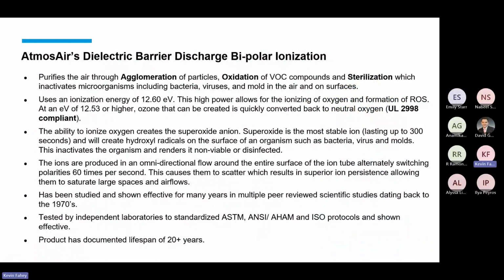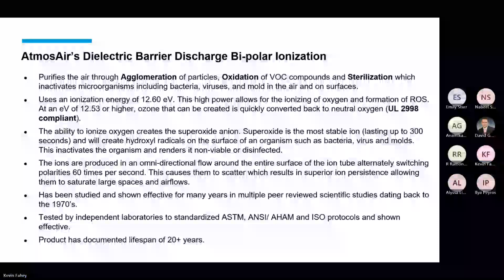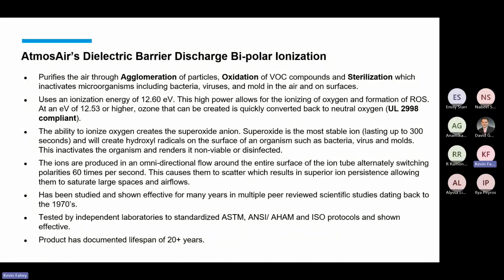Here it is. So three things. Agglomeration is particles getting larger. They either fall out of the breathing space, and I'm talking about nanoparticles, particles that are less than 2.5 microns in size. These are the particles that will get into your lungs and get into your bloodstream and really are irritants for people who have allergies and asthma, things of that nature. So it agglomerates these particles, they fall out of the breathing zone, or they're more easily picked up by a filter. ASHRAE did a study that showed the impact of the combination of MERV 13 filters with our technology and how it made it much more effective, and I'll show you that toward the end of the presentation. But agglomeration is one of the features.